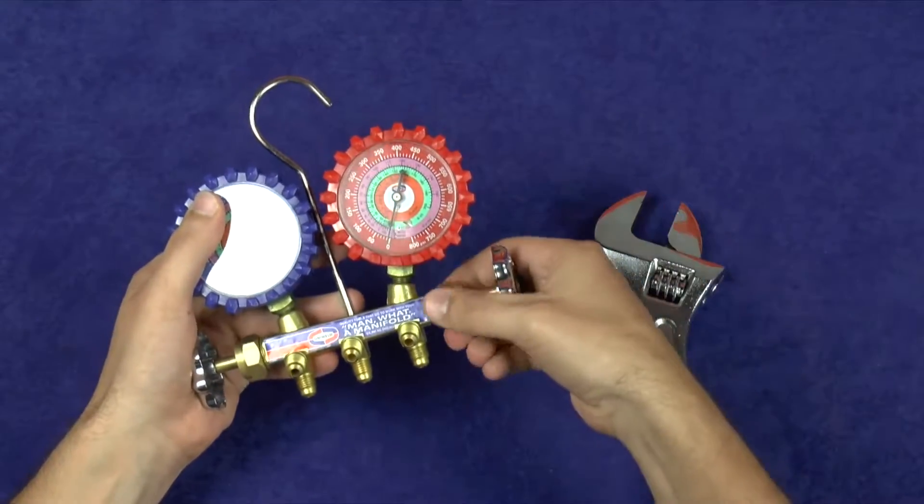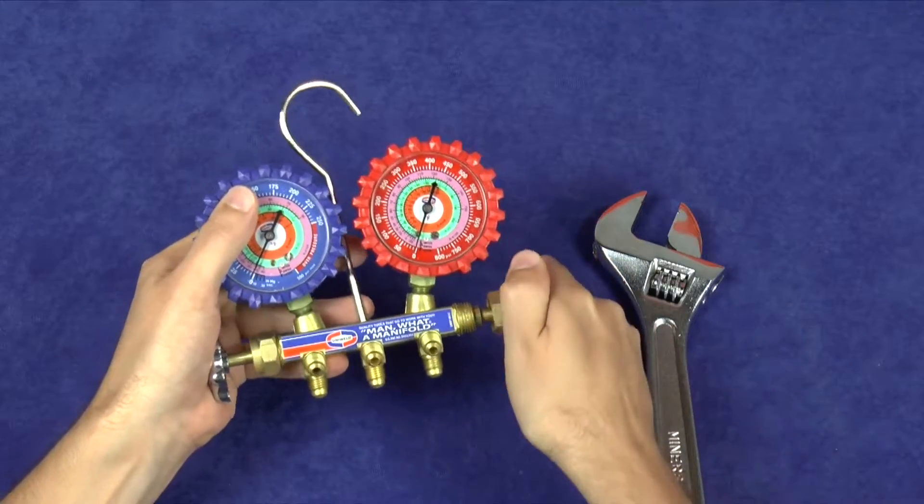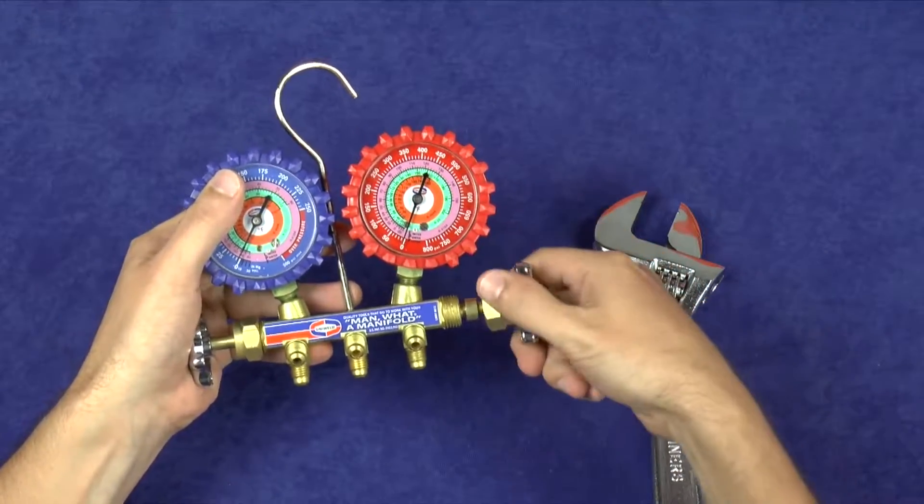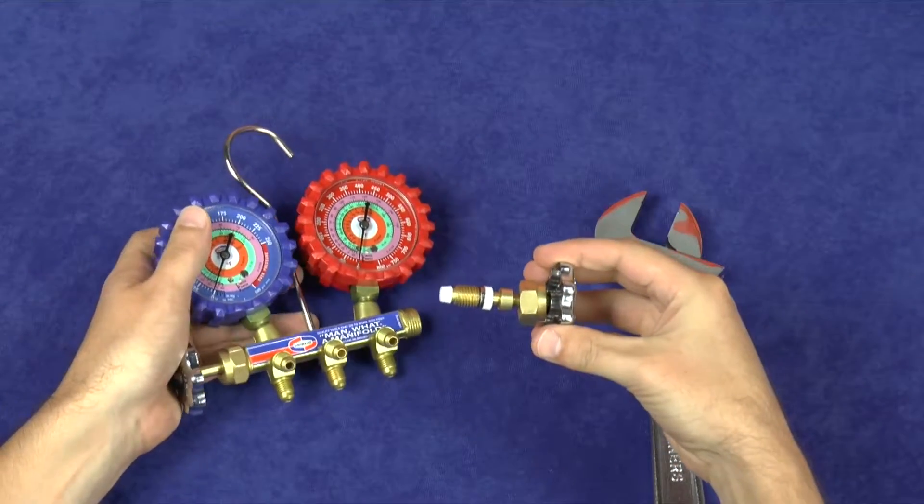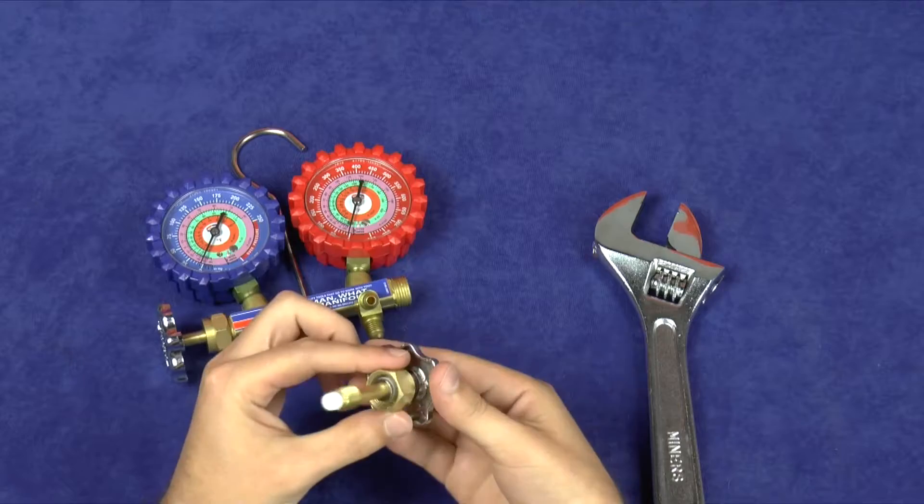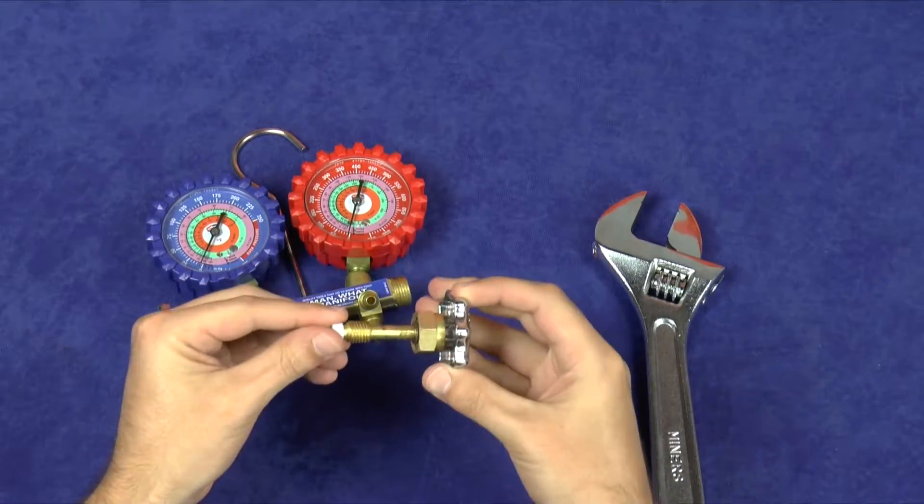Unscrew the brass packing nut and remove the valve stem assembly from the manifold body by turning the metal hand wheel counterclockwise. If any foreign debris has found its way inside, it can score the Teflon and prevent it from sealing properly.